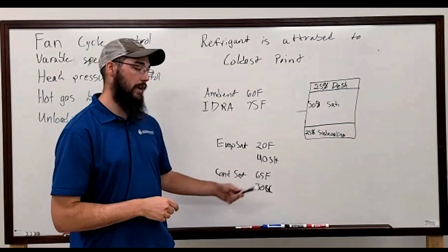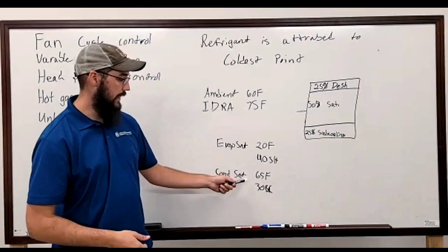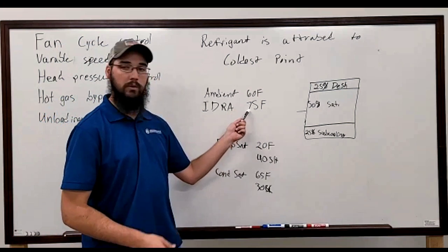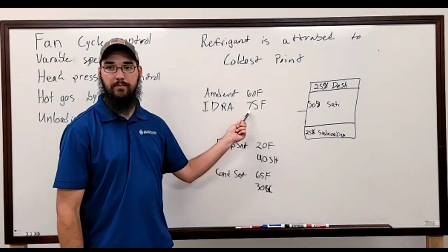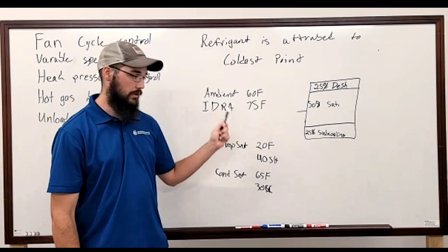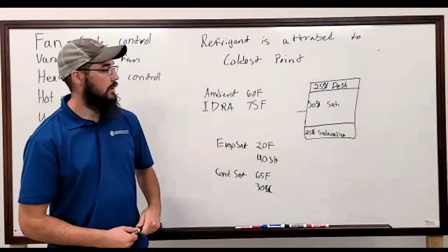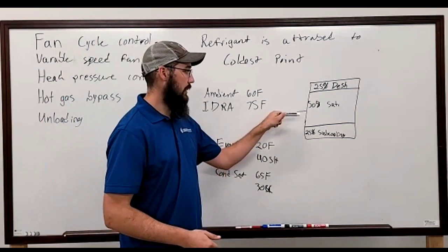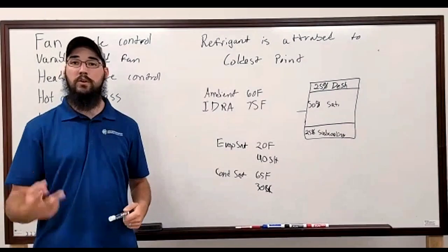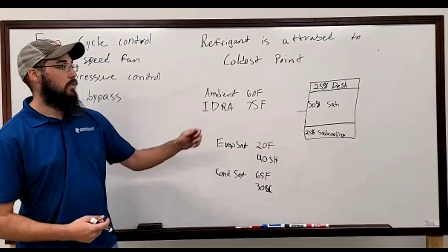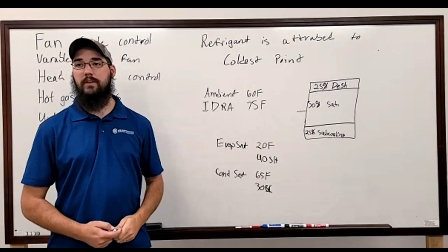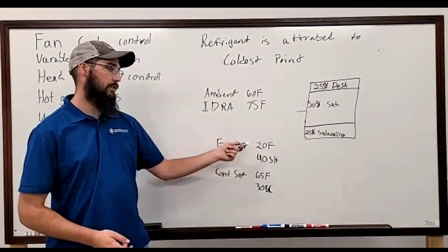What it is, you're in a low ambient. Your saturation specifically has dropped below your indoor return, which cannot happen. You will see this condition in that state. So if you ever question if this is the case, say you're working on a split system or an RTU, either or, walk up to the common leg of your condenser fan motor and pull it. And let your head pressure start to build.